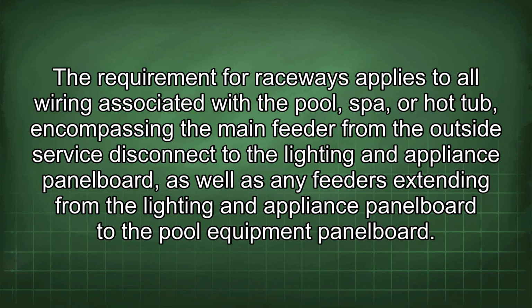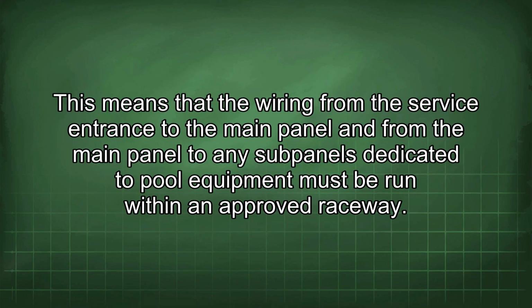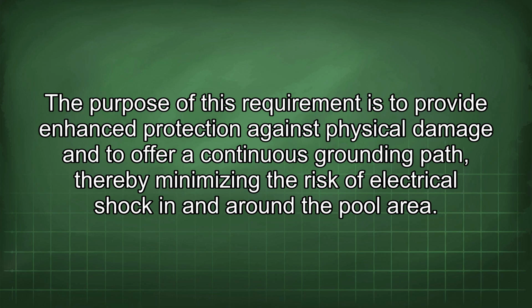The requirement for raceways applies to all wiring associated with the pool, spa, or hot tub, encompassing the main feeder from the outside service disconnect to the lighting and appliance panel board, as well as any feeders extending from the lighting and appliance panel board to the pool equipment panel board. This means that the wiring from the service entrance to the main panel and from the main panel to any sub-panels dedicated to pool equipment must be run within an approved raceway. The purpose of this requirement is to provide enhanced protection against physical damage and to offer a continuous grounding path, thereby minimizing the risk of electrical shock in and around the pool area.